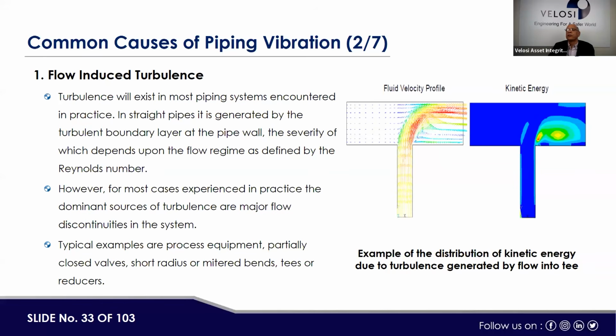Do you need to do a vibration survey, or does it depend on the issue? See, visual surveys, visual inspections, are done for the piping systems. And if you see some vibration issues, then you have to carry out measurement of the vibrations to check whether they are within the acceptable range or not. And it's a part of normal life, because we have to have some sort of inspection for the piping, for equipment, for instruments, for all assets we have on the facility. We have to have a normal inspection program, and under it, the requirement of vibration surveys would also arise if we see some problems appearing on the piping systems as well.